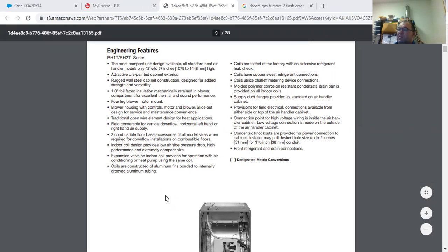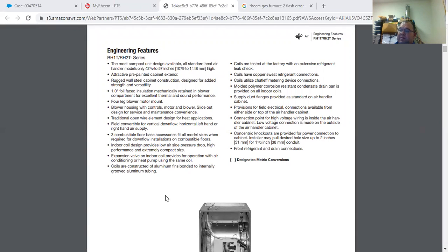Indoor coil design provides low air side pressure drop, high performance, and extremely compact size. The expansion valve on the indoor unit provides operation for both air conditioning and heating. So the coil will work for both heat pumps and air conditioning. The coils are constructed all aluminum except for the copper braze fittings. These coils are tested at the factory with an extensive refrigerant leak check. Coils have copper sweat refrigerant connections, which is important. Big bonus here, they utilize the Chatleff metering device connections. So if you do have to replace a TXV, you basically have 3 bolt-on connections.